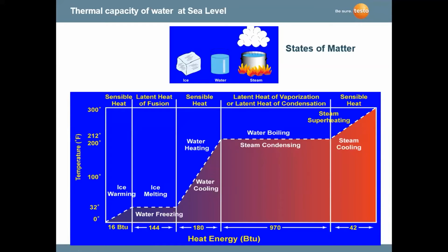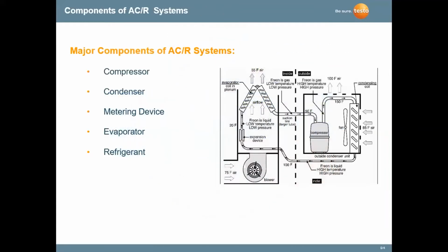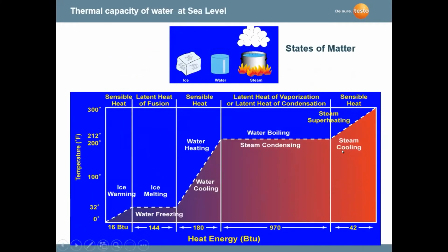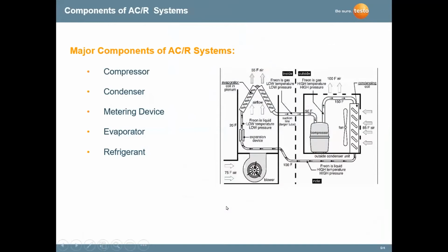Like I said, water is very visible. So we know where the boiling point of water is, at 212 degrees. When you're dealing with R22 or, for example, R410A, they have much, much lower boiling points. For instance, R22 boils at minus 41 degrees Fahrenheit. 410A boils at around minus 61 degrees Fahrenheit. So here, the level line is where we have what we call saturation. We have a change of state, and that occurs in our coils. If we go in reverse and we reduce the heat, then we're changing from a vapor to a liquid.